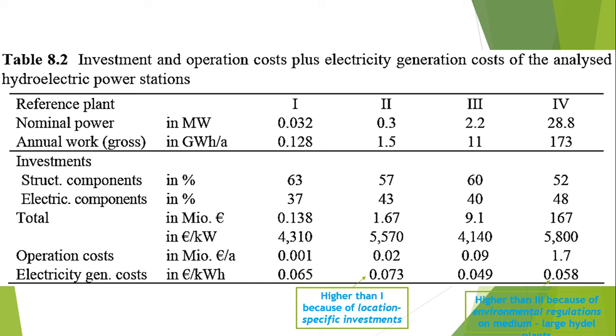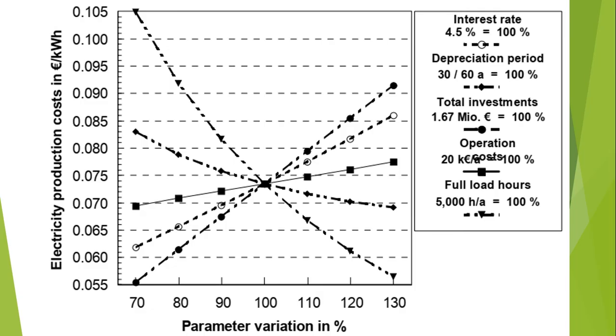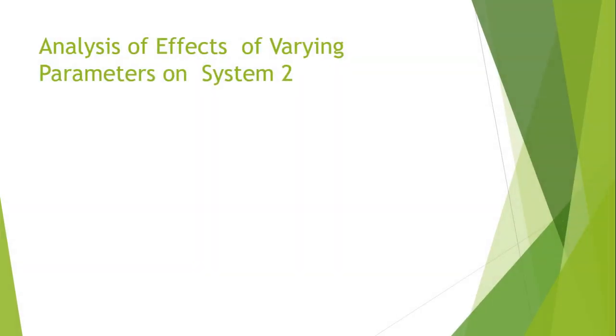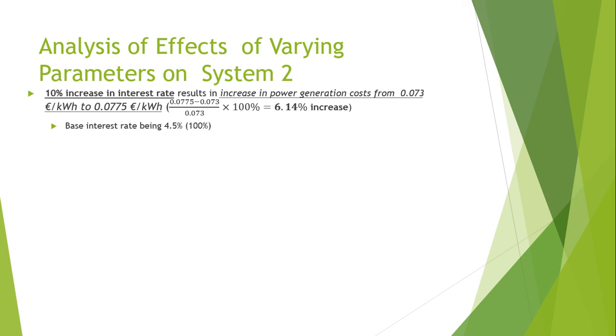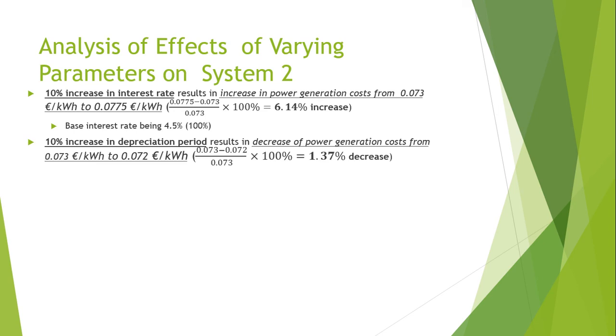This higher cost for plant 4 is mainly because of environmental protection regulations being imposed on that plant. The specific electricity generation costs are normally lower if already existing plants can be reactivated or modernized, in spite of the higher level of dependency on local conditions. Under such conditions the cost would be between 0.03 to 0.08 euros per kilowatt hour.